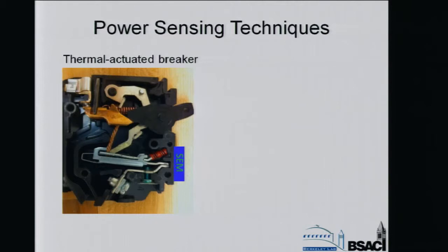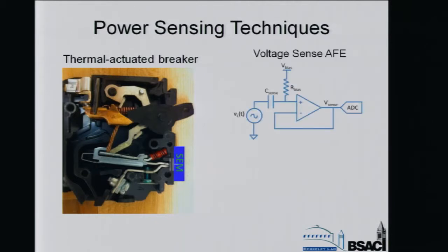So again, here's a thermal actuated breaker with our sensor annotated. To measure the power, we need voltage and current. To measure the voltage, there's a capacitance which is created between the high voltage energized conductor in the circuit breaker and our SEM sensor PCB. So as the line voltage changes, this induces a current through that capacitor, which is then sensed by the circuit shown here on our PCB board.